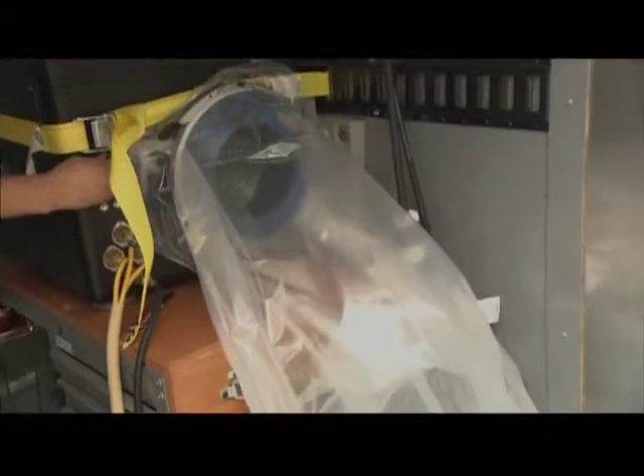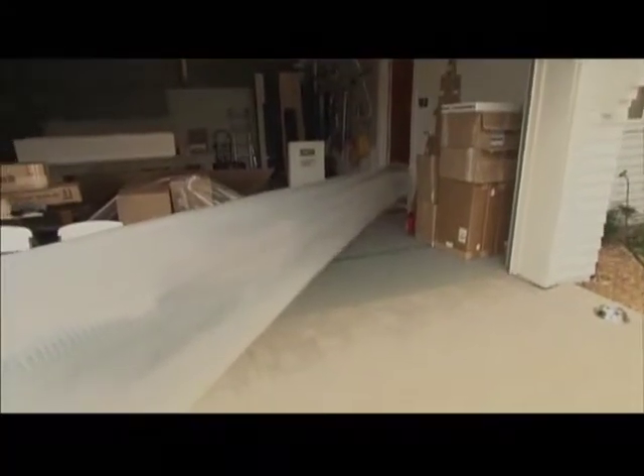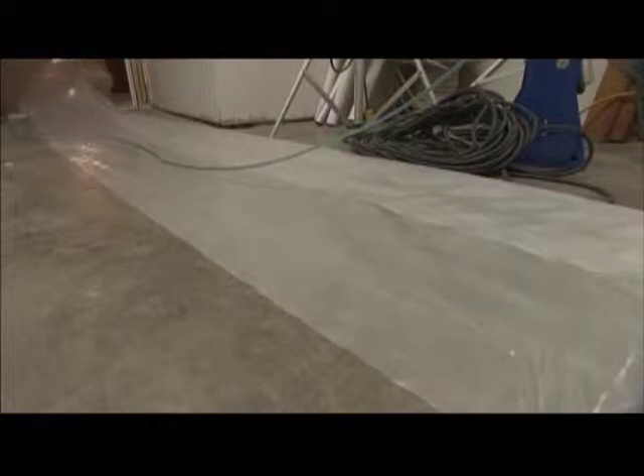So how exactly does that work once you start injecting everything? Basically what we're trying to do is put the ductwork under pressure. We take a liquid sealant, heat it up, turn it into an aerosol, and inject that into the ductwork, forcing it out the holes so we can start sealing them.